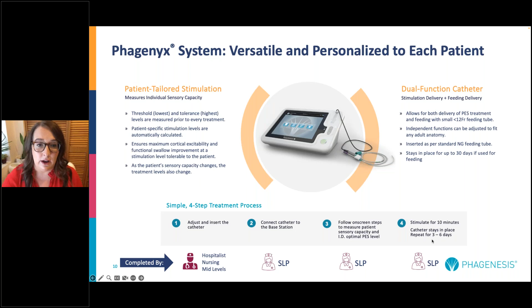I get a lot of questions about electrode positioning. So the foundational studies use brain imaging to optimize the therapeutic target region in the pharynx, in the throat, for pharyngeal electrical stimulation. As I highlighted before, the nasal black and oral green positioning guides, which were based upon average adult anatomy ranges, ensure correct placement of the catheter. So to confirm the electrodes are in their proper position in the pharynx, as shown above, and I've got a little animation here. When the stimulation is being delivered, you can think of it almost like an olive. It's not so focal, it branches out and hits many regions within the pharynx.